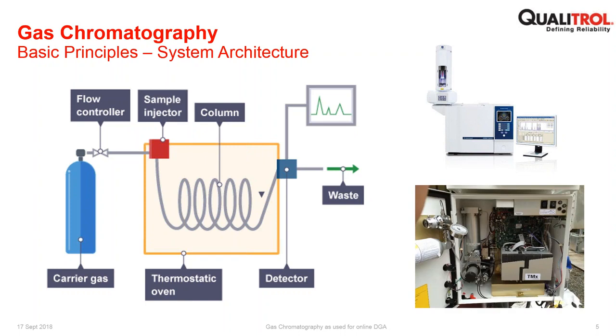And this is just the inside of a Serveron unit, for illustration of what it looks like as an online system. There is a sample preparation and injection system here. What is marked here with the badge TMX is essentially the oven and the detector system. It may not be possible for you to see, but it is lined with insulation. This is to help keep it at a stable temperature, as of course is the oven in a laboratory GC, and thermal control is achieved in there. And then, of course, in the online system, there is a range of control electronics and communication. What's not shown on either the top or bottom photograph is the carrier gas. The carrier gas will be a cylinder connected directly into the laboratory system or into the online system, supplying it with carrier gas, in one case helium, in the other case argon.